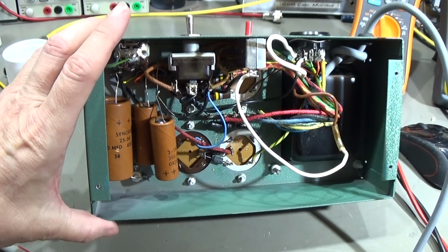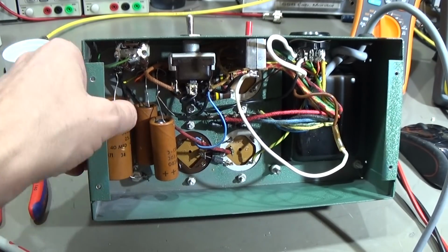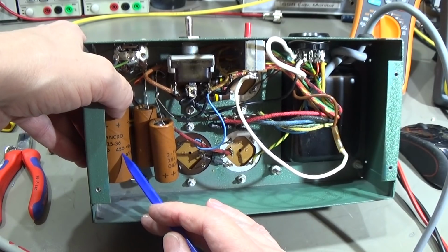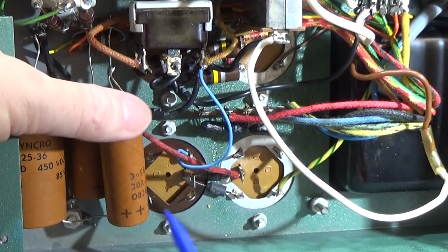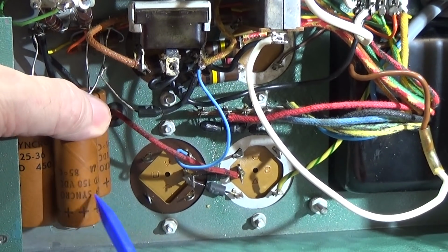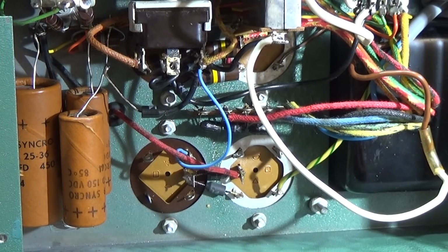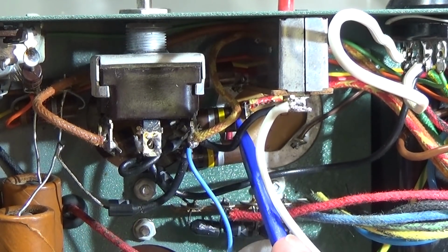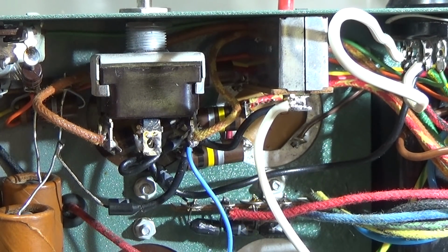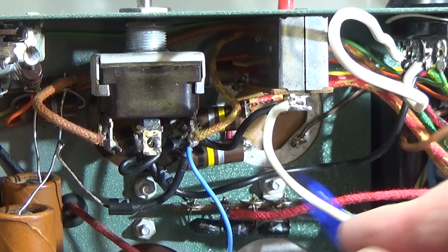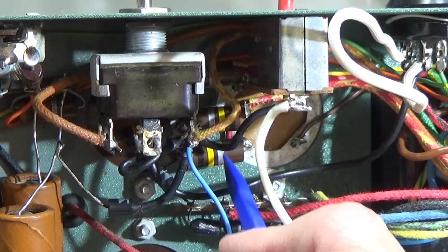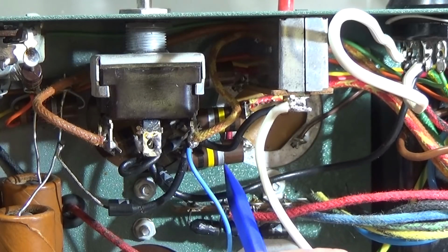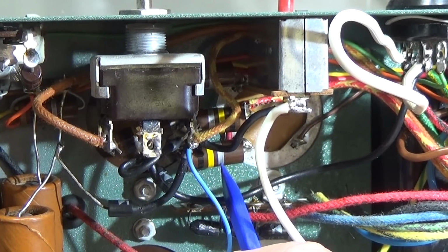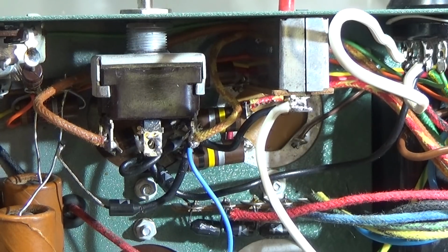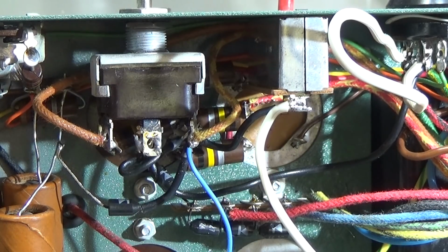And of course we need to check these capacitors as well. The big one here is a 450 volt version. These two little ones are 150 volt DC, and I need to check these old carbon resistors, because they're known for running out of tolerance, even the silver ones at 20% tolerance, if I'm not wrong. Today a silver tolerance ring isn't seen so often, because it's much easier to produce better tolerance now.